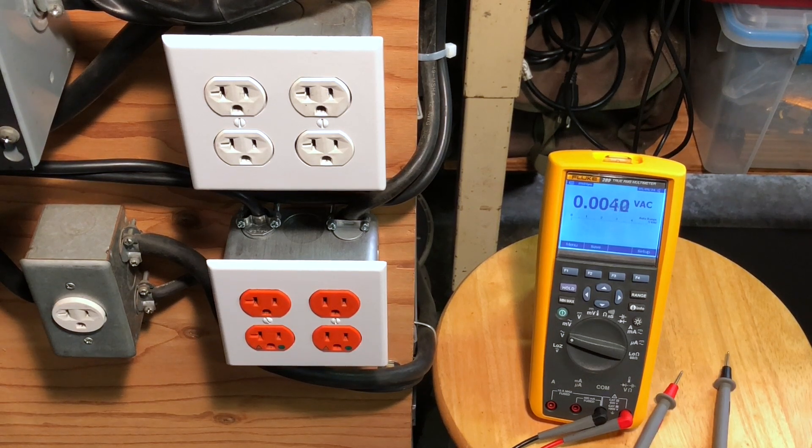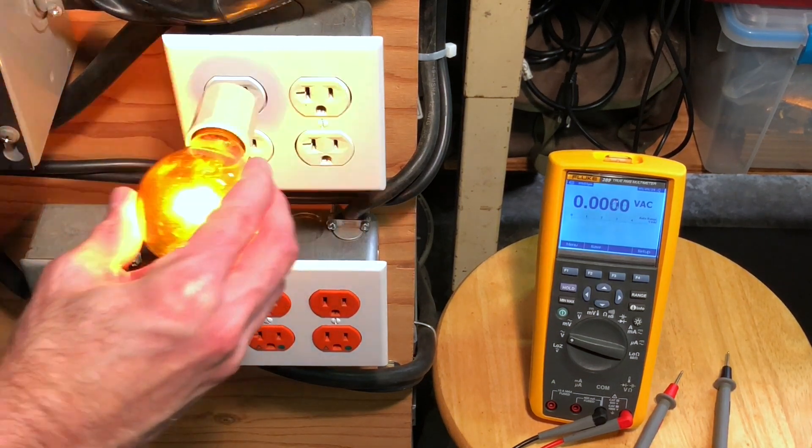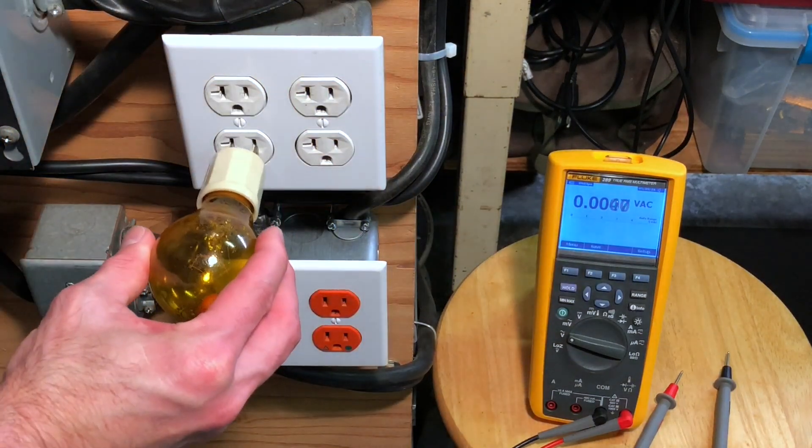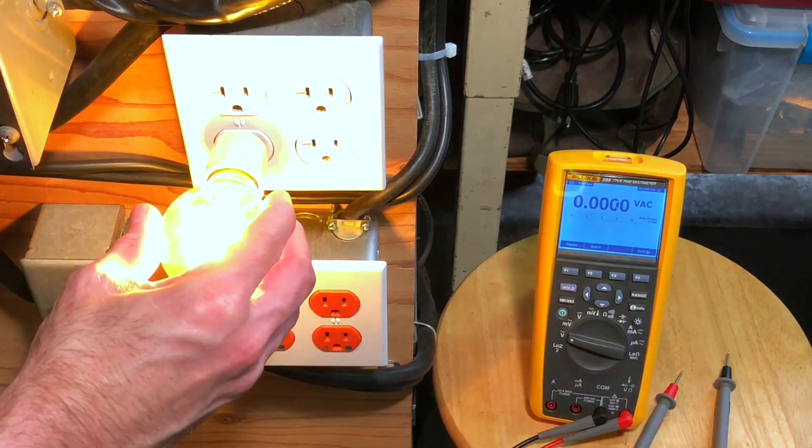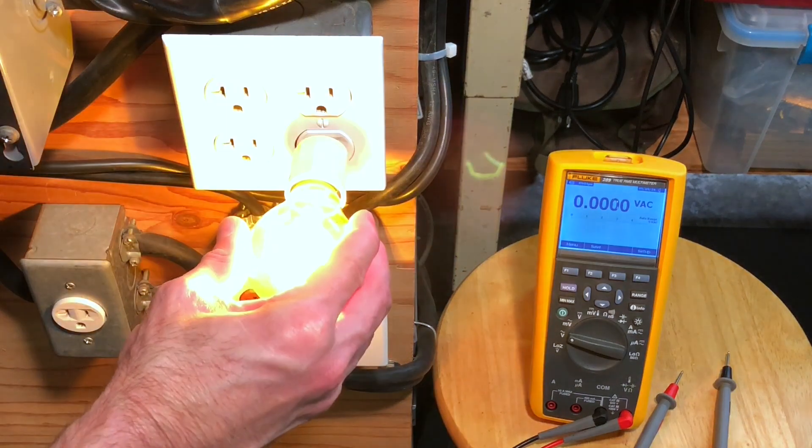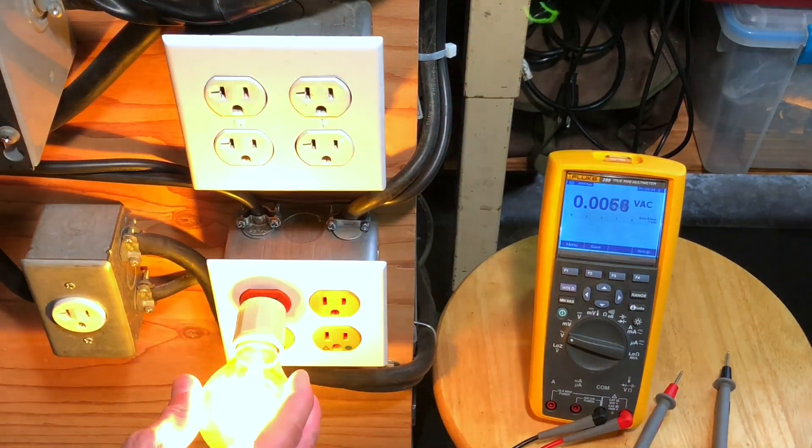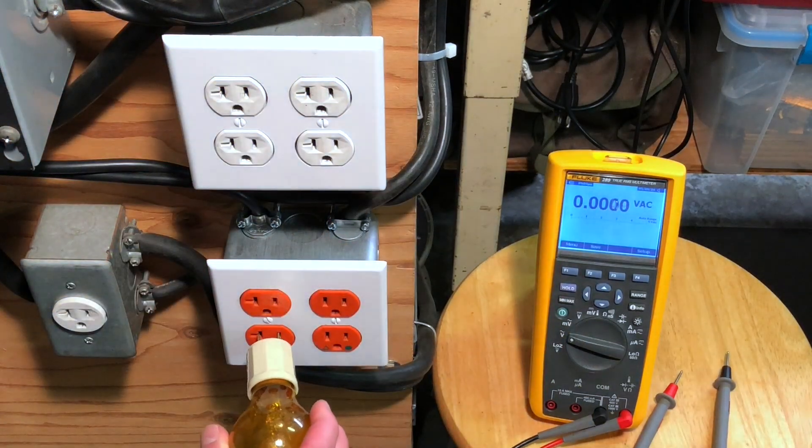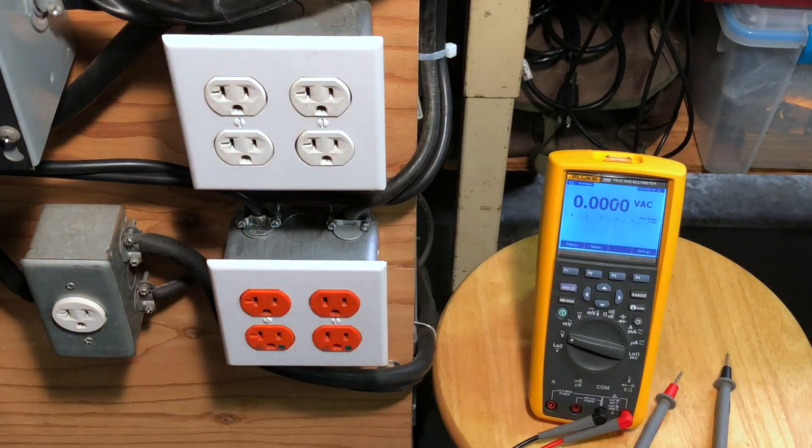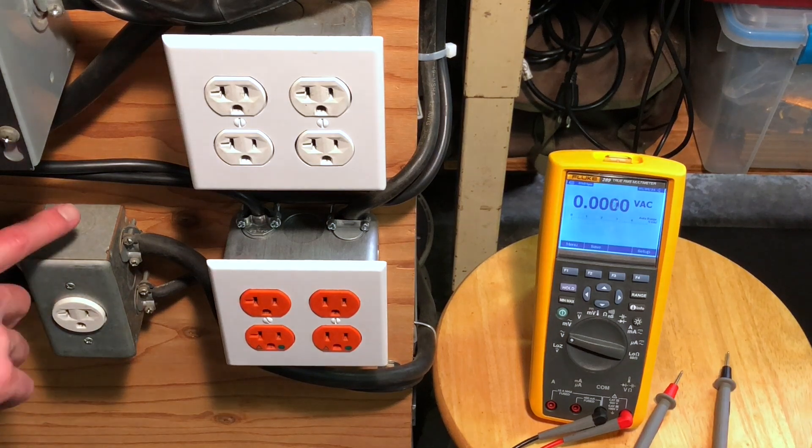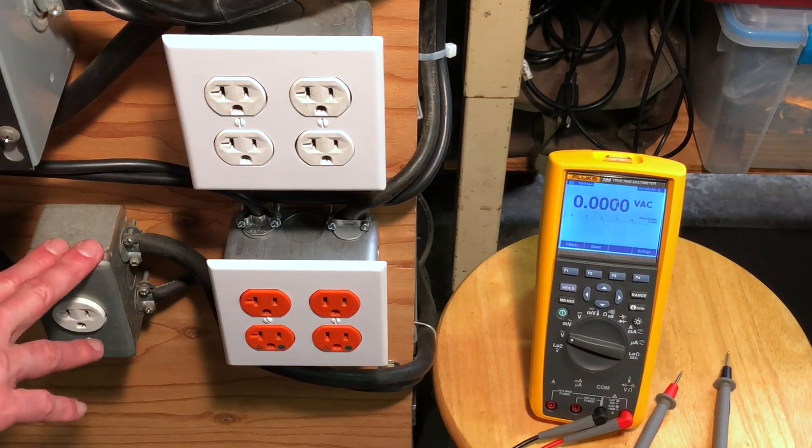It's important to have isolated ground outlets like this because if a fault ever occurred and a voltage appeared back on the ground wire and fed back in here from a piece of equipment you were troubleshooting, you would not want this box to become electrically hot. That could be a hazard or a problem. This just isolates this box from this ground connection. To demonstrate that these outlets are in fact electrically live, I have my test bulb right here.